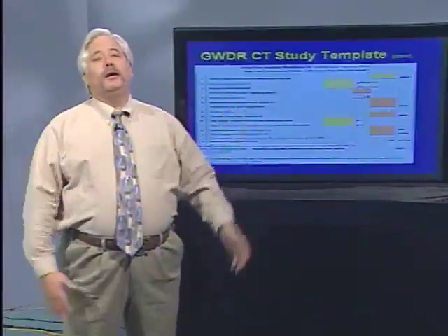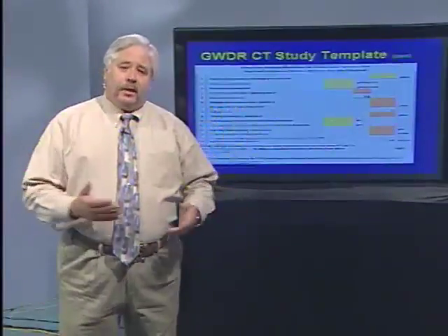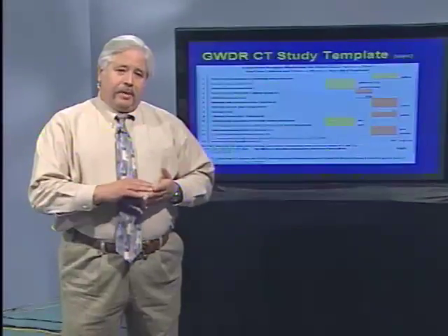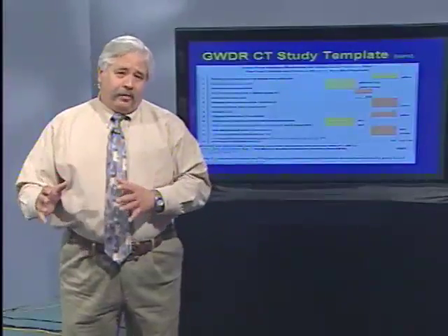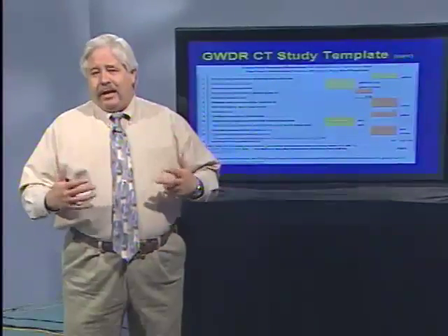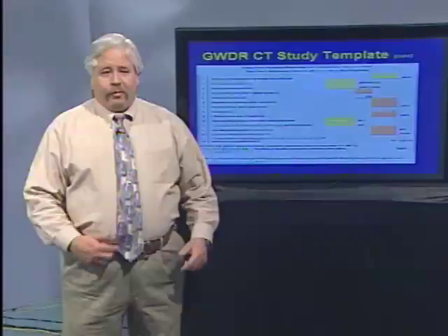Let's see, what else? Free chlorine. Oh, it's the ground storage capacity. The storage capacity at that facility has to be at least 30 gallons for every gallon per minute of flow through the plant. And it'll become kind of evident why that's the case as we get further into the form.